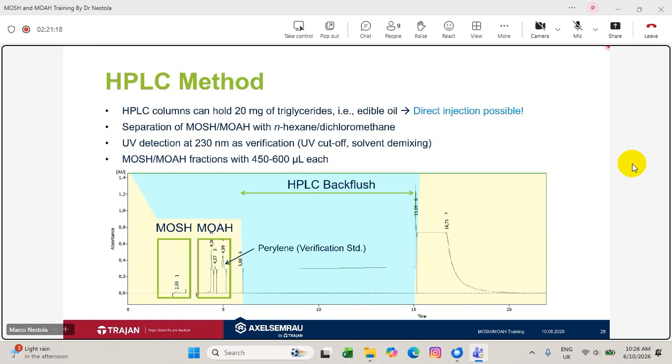What if the LC columns are contaminated or damaged by aqueous samples? Normally, when you do not have salt inside, when it's only water, you can flush it with isopropanol, and then again DCM, hexane. As long as you have not injected salts, because when it is a salty solution, it's quite complicated to get these out again, because salts typically have metal ions in them.